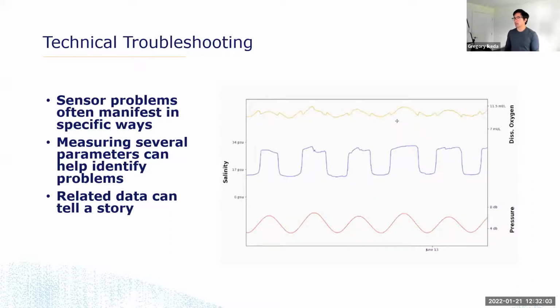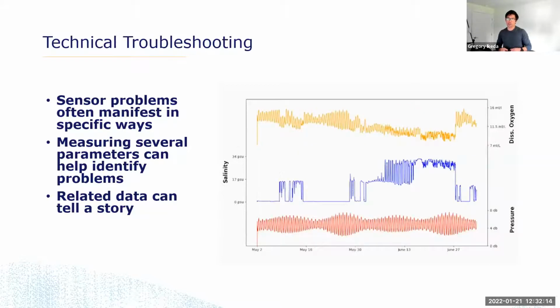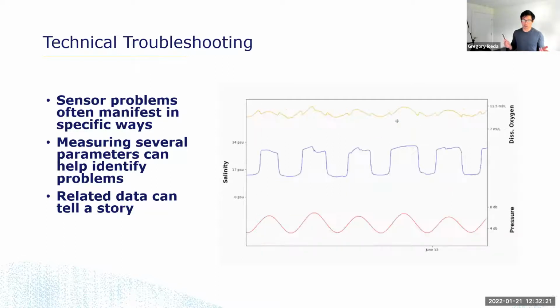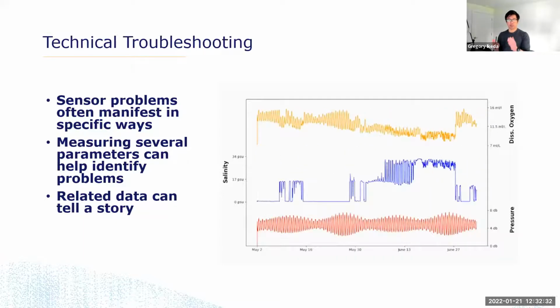So I'm looking at dissolved oxygen for clues, I'm looking at salinity for clues, I'm pulling up pressure to see if these are matching the tidal cycle. Having all of these parameters tells me a lot more. If I were just looking at dissolved oxygen, I might say, wow, the magnitude of oxygen concentration is changing quite a bit. I don't know why it's got this regular pattern. I don't know if this is real, but having salinity to look at tells me there's something going on with my instrument that needs to be addressed. Having pressure to look at tells me there is a regular pattern that is being influenced by the tides.